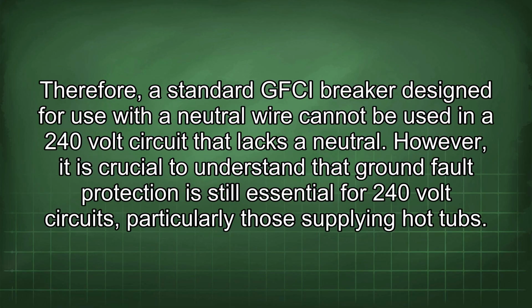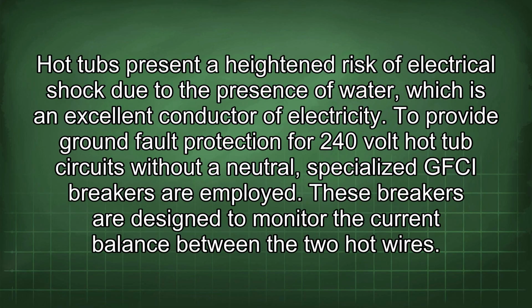Therefore, a standard GFCI breaker designed for use with a neutral wire cannot be used in a 240-volt circuit that lacks a neutral. However, it is crucial to understand that ground fault protection is still essential for 240-volt circuits, particularly those supplying hot tubs. Hot tubs present a heightened risk of electrical shock due to the presence of water, which is an excellent conductor of electricity.